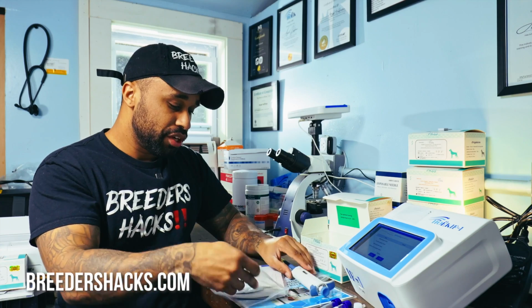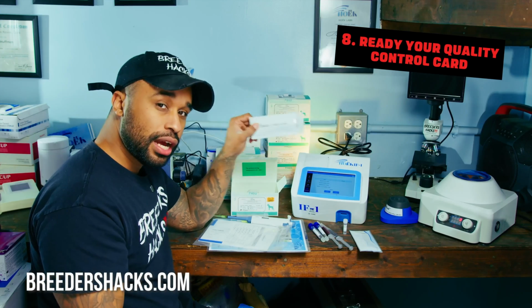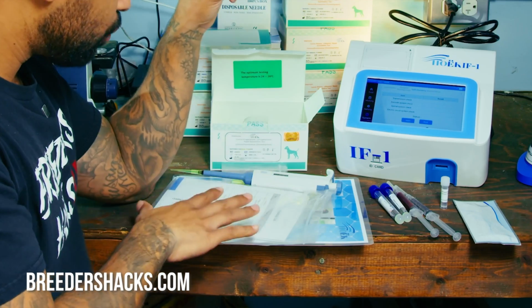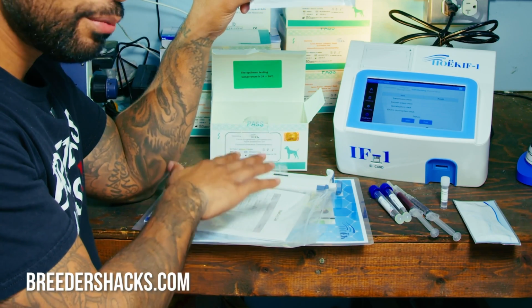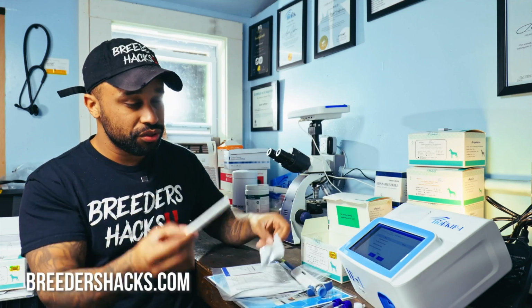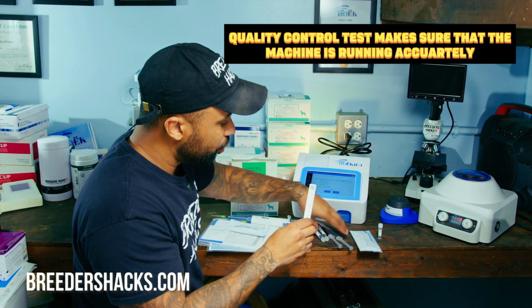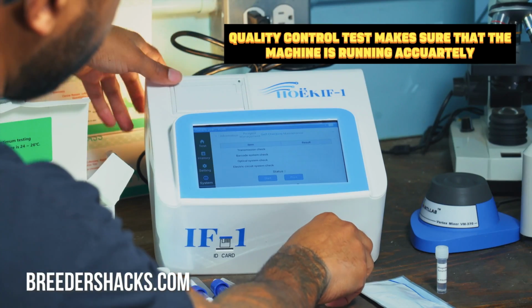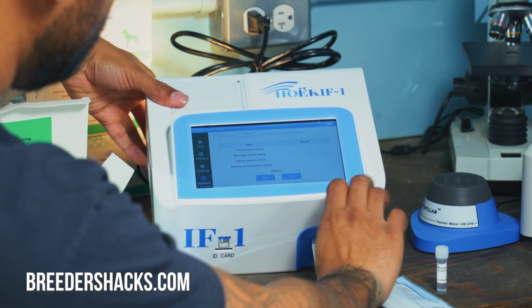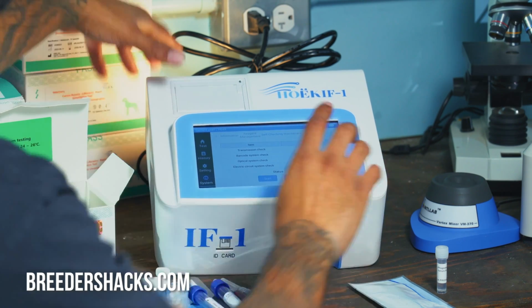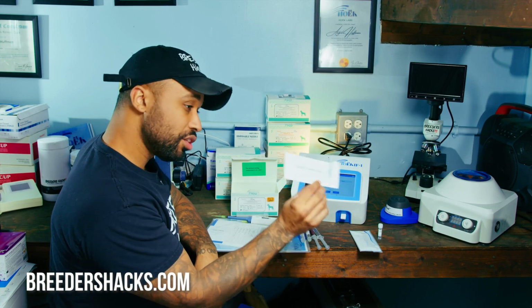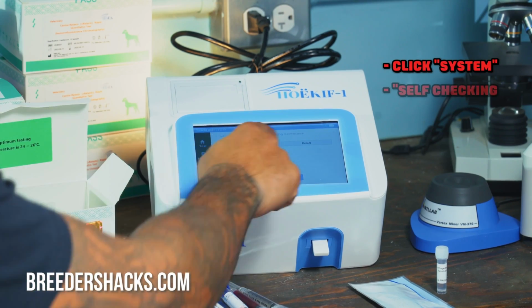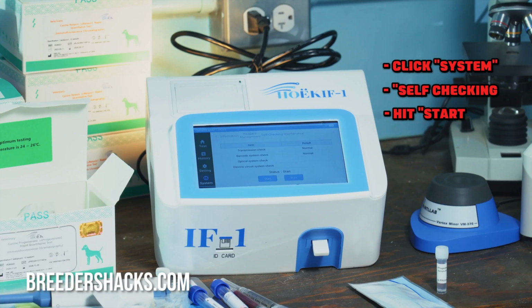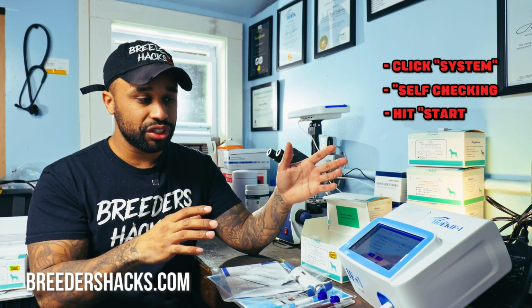What we're going to do is take our quality control card. I want to make sure you guys do not lose this thing - that's why I said you're going to keep it with your paperwork for your machine, because every time I start this machine to use it, I use the quality control. All it is, is a quality control to make sure the machine is running accurately. We got the machine tilted so you guys can see it a little better, but let me get this in here like this. Boom - so we put our quality control test right in the machine. And then now all we have to do is hit system, go to self-checking, and hit start. What that's going to do is allow the machine to do a test run and make sure that everything is running accurately.